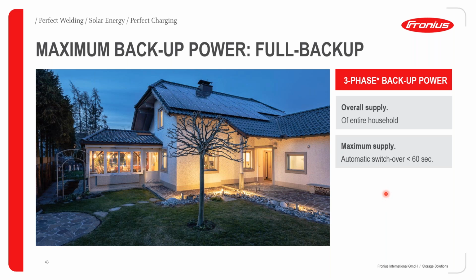And therefore, the poll that was launched by my colleague is also quite important for you to be able to know which battery system or which inverter system you should be using from time to time. So if you are in a stable grid area, the Gen 24 Plus, of course, is a very good inverter for you to use. However, if you are in an area where the grid keeps on failing from time to time, and you want automatic transfer of power when the grid fails, maybe the Gen 24 might not be the best option for you. Therefore, we can discuss the AC coupled configurations with the Fronius and Victron kind of setup that might give you better transition times when there's a grid outage. So the Gen 24 basically is an inverter designed to increase the self-consumption of generated PV energy.